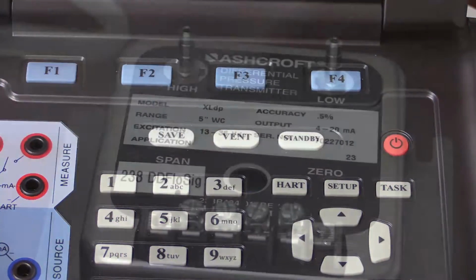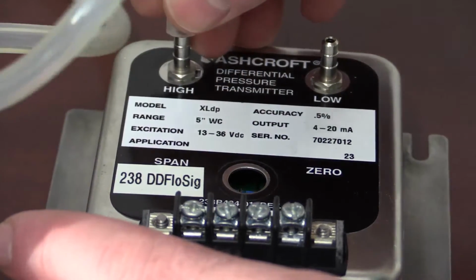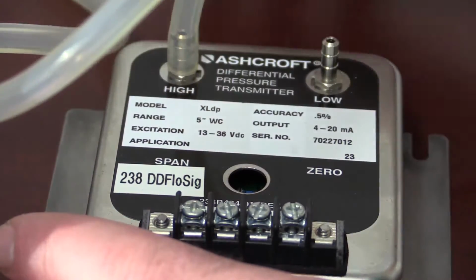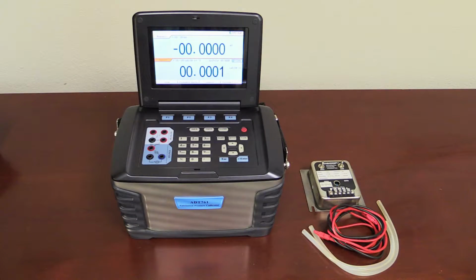In this video, we will demonstrate how to use the ADT761 to calibrate a differential transmitter. In this example, we will be calibrating a 0 to 5 inches of water Ashcroft differential transmitter.